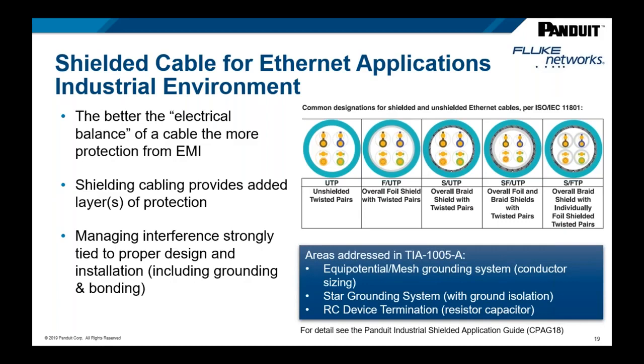The balance is the dimensional and electrical symmetry between each pair. The CAT-6A cable standard actually requires this symmetrical design dimensionally and electrically, so using CAT-6A cable, you know it has better balance and EMI noise immunity than previous cable types. We're seeing a lot more CAT-6A cable being used on plant floors.